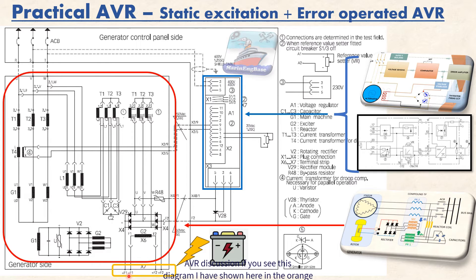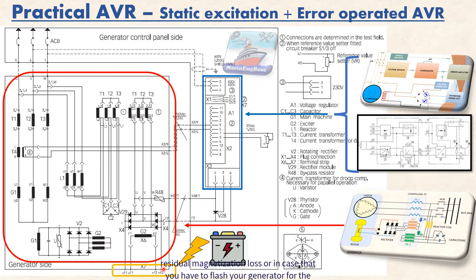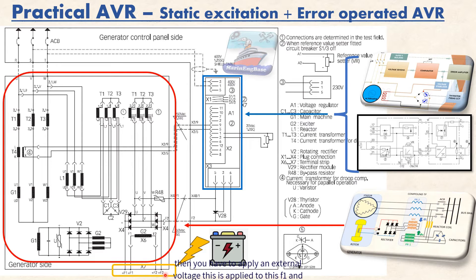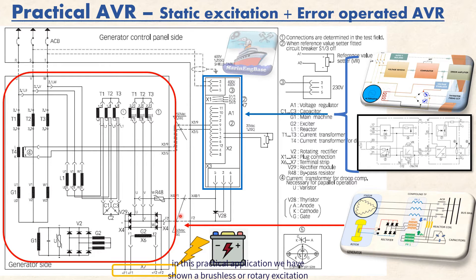In this diagram, I have shown in orange color with a battery symbol — these terminals are provided for field flashing. In case you have lost residual magnetism, or in case you have to flash your generator for the very first time, you have to apply an external voltage. This is applied to the F1 and F2 terminals. In this practical application, we have a brushless or rotary excitation system.